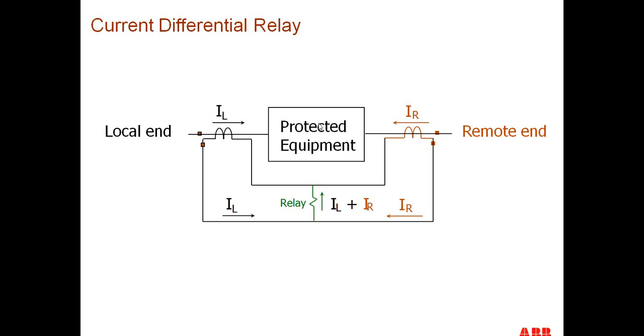A current differential relay in itself just looks at the protected equipment, which can either be a transformer, a line, a bus, or whatever, and we take a current on each side of the piece of protected equipment, hook the current transformers up so that polarity is away from the piece of equipment, so that the currents are both in towards the relay, and we virtually measure the current going into the protected equipment and out of the protected equipment. If we have through load current or a through fault, the current is running into the device and out of the device, and so IL and IR are equal to each other. If there's an internal fault, then IL is not equal to IR, and the current all goes through the relay coil, and the relay operates.